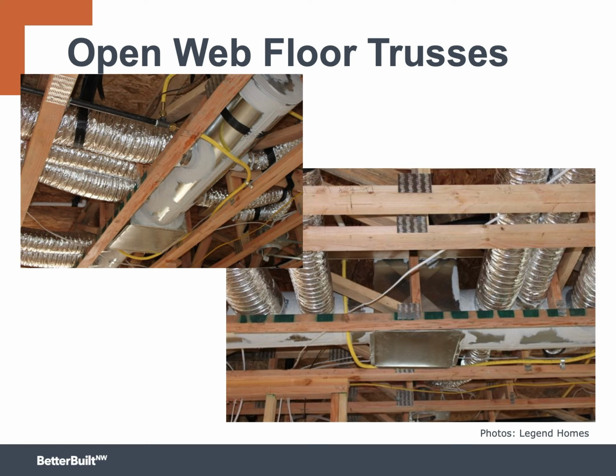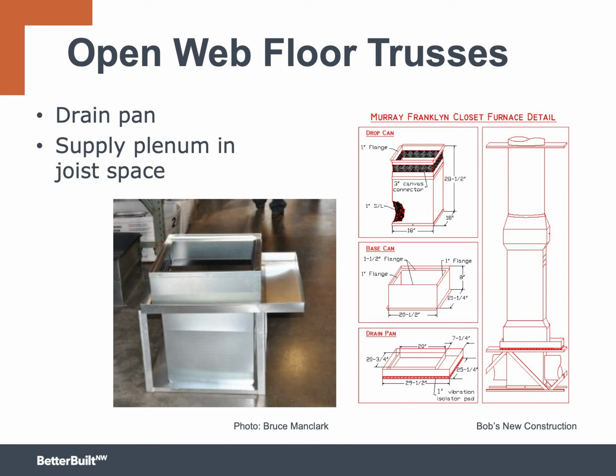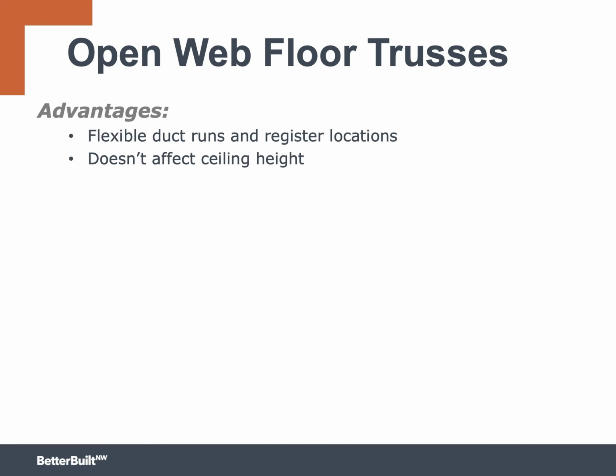Placing the furnace on the second floor means there will be condensate from the condensing burner in the furnace and the air conditioning coil. Since the air handler is inside, it's a good idea to put a drain pan under it, but the base can gets in the way. Here's a clever idea that was developed by Bob's New Construction in the Puget Sound area. They've created a custom base can assembly that includes the drain pan. It's essentially wrapped around the base can. There is no possibility that condensate or leakage could drain into the supply ducts. Each of the 3 sections overlaps the section below it. Some builders choose to skip the drain pan and use a moisture alarm instead.